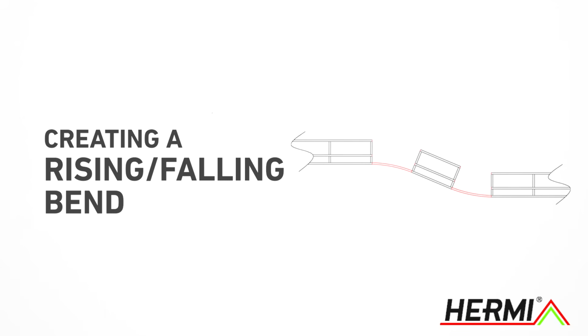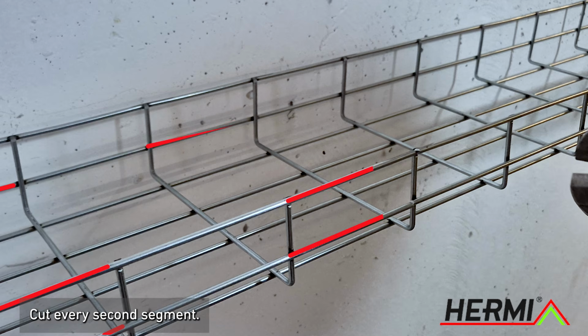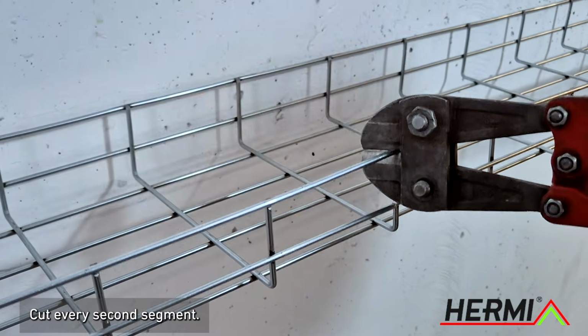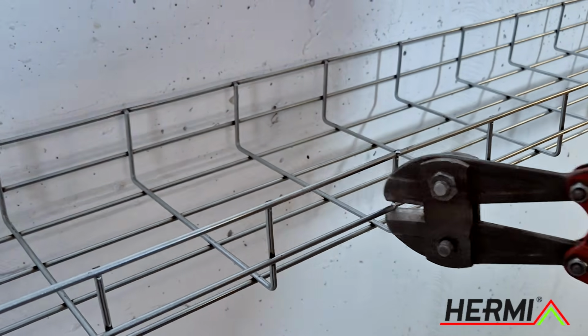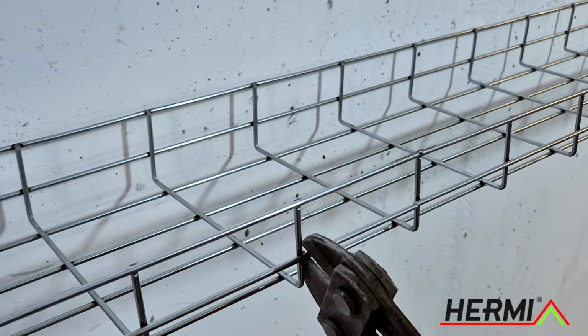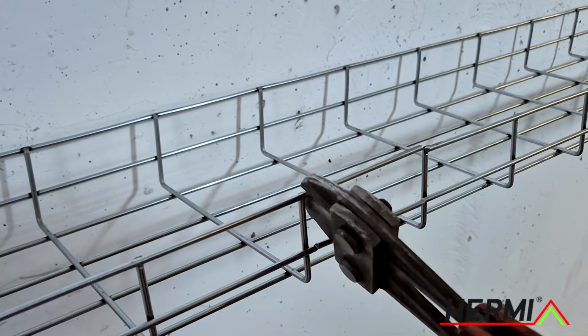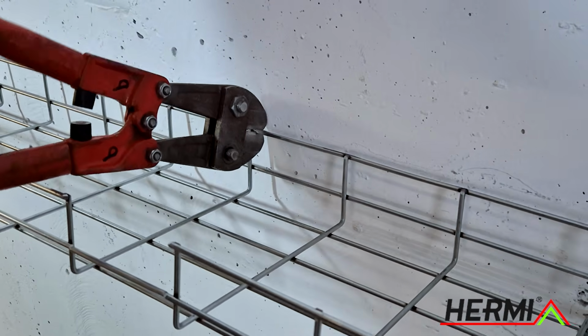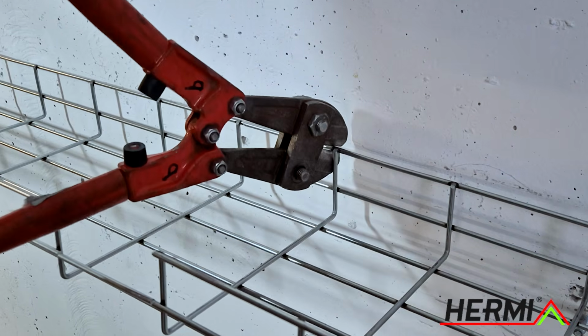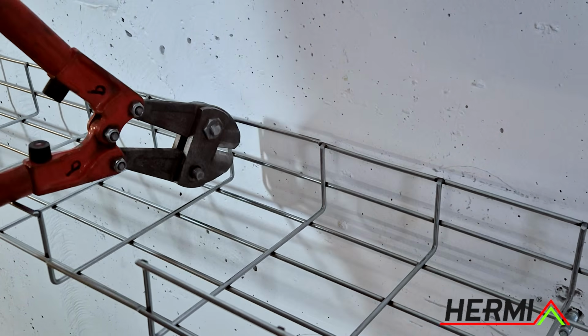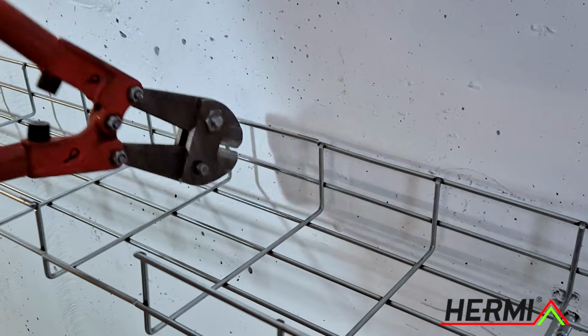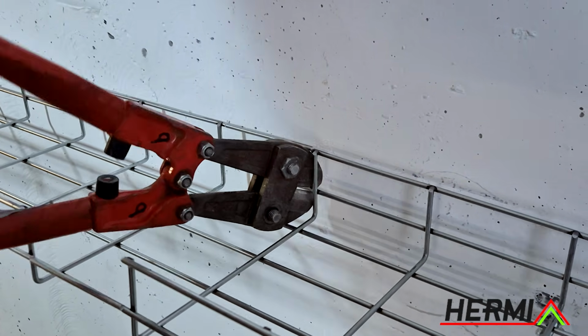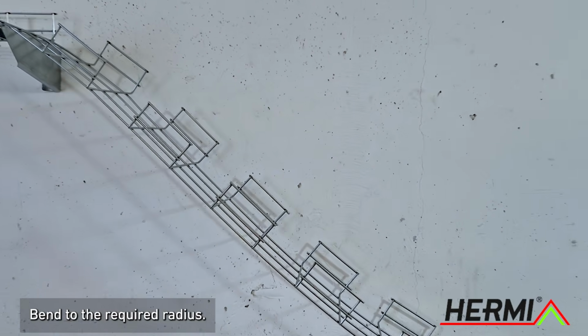To create a rising or falling bend, cut out every second segment along the edges of the mesh cable tray, depending on the required angle. Bend the mesh cable tray to the required radius.